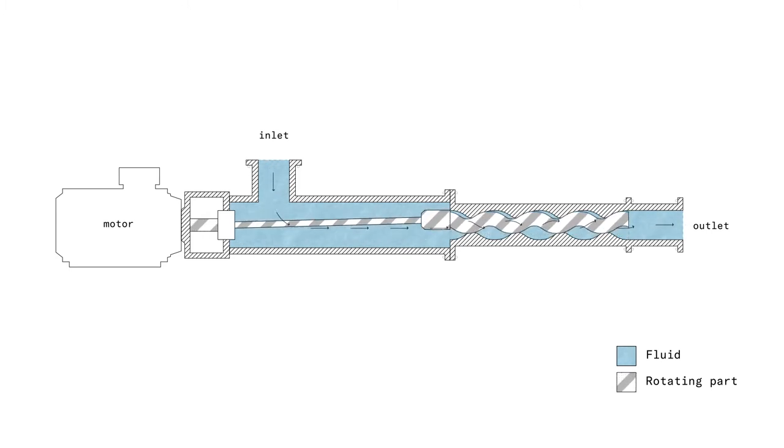This is how the PC pump works. Let's talk about the applications. A PC pump can be very gentle to the products that it's moving — for example, polymers. Polymers we want to work very gently with because they are shear sensitive; we don't want to break them into small pieces. For that, a PC pump is an excellent choice. But we also sometimes have fluids with suspended solids, and a PC pump is also excellent for products with suspended solids.